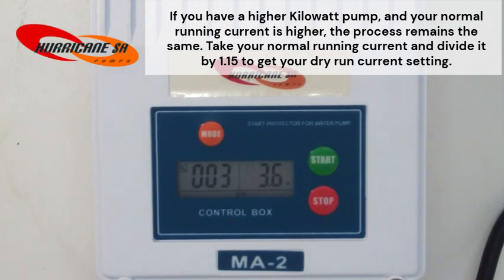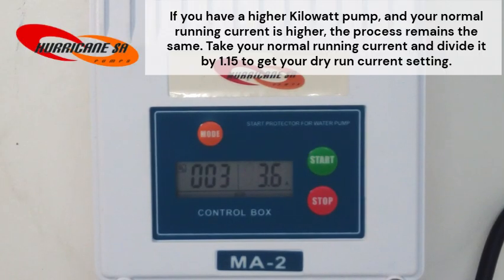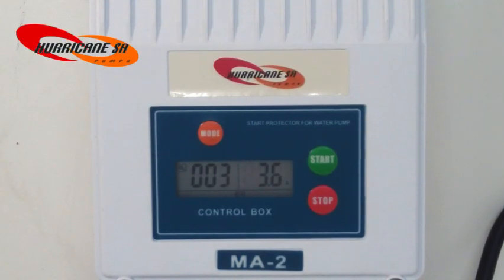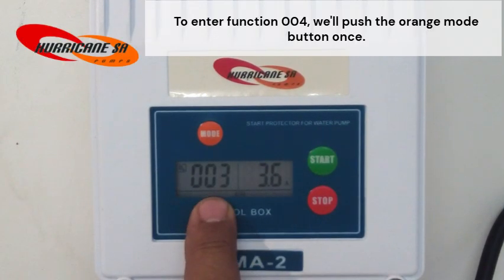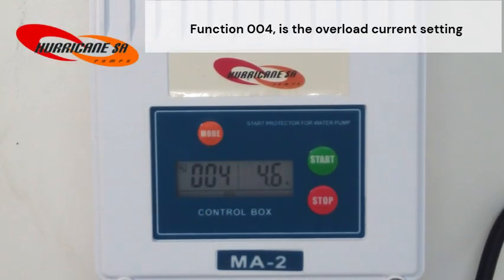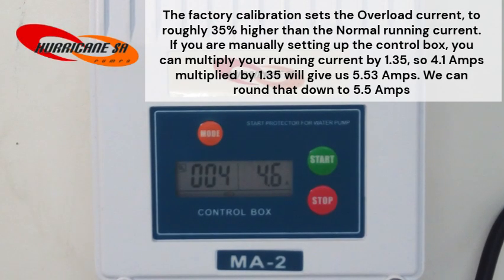If you have a higher kilowatt pump and your normal running current is higher, the process remains the same. Take your normal running current and divide it by 1.15 to get your dry run current setting. To enter function 004, we'll push the orange mode button once. Function 004 is the overload current setting.